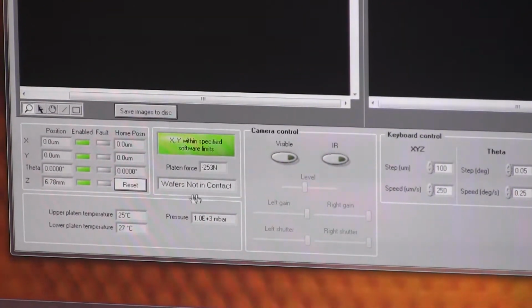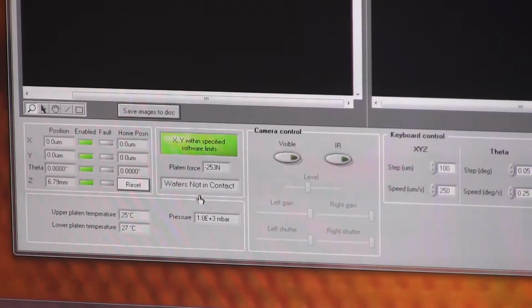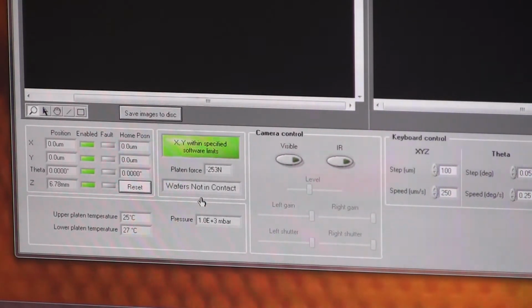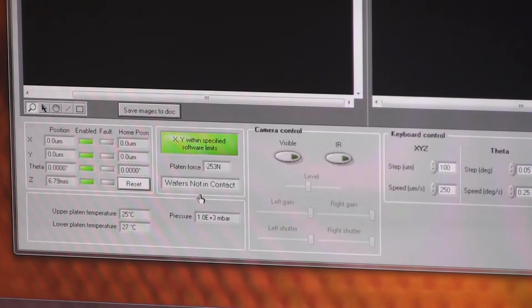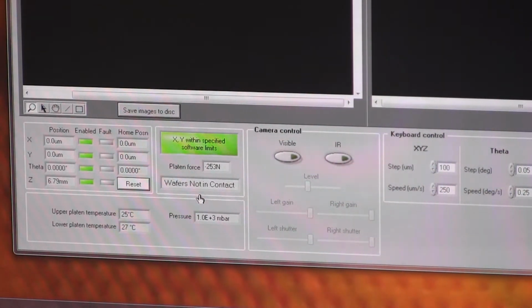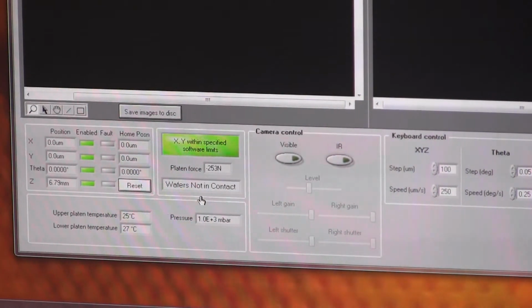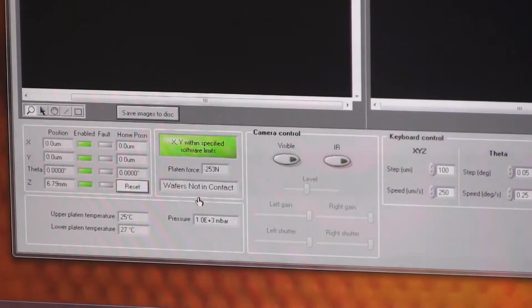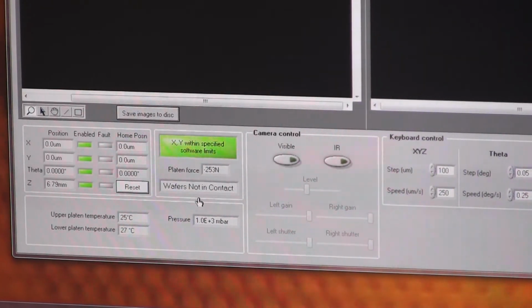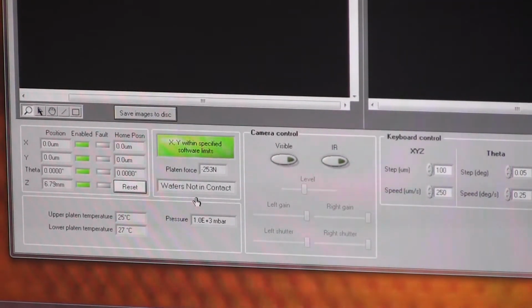The software will tell you if it thinks the wafers are in contact. It determines that if there's a force of more than 20 or 40 newtons or so, and will tell you the wafers are in contact. If the software believes the wafers are in contact, it won't allow you to move the manipulator, because there's no point trying to move the wafer once it's touched.